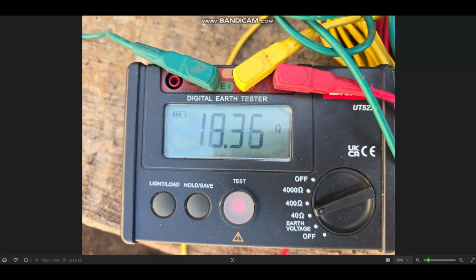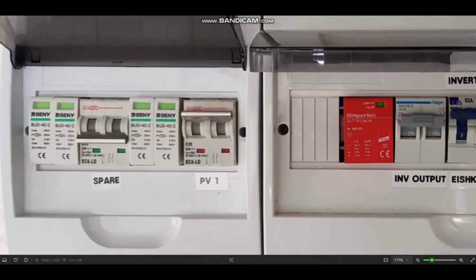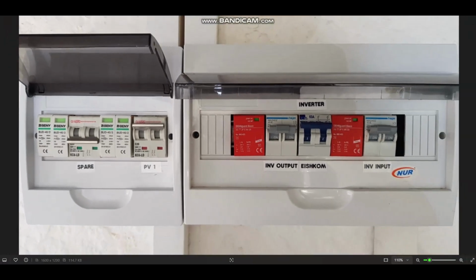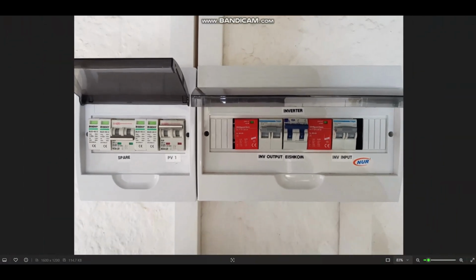What the earthing system is then linked to is a DC sub-DB, another distribution board. Here we can see, and again, you will need more surge arresters in the event that that voltage is exceeding what it should be. So at this point, I think it's important to mention the fact that what we've done here with the safety and surge protection system is to put high quality airbags, electronic stability program, ABS braking, your airbags, your crumple zones, your rebar zones, things like that. But it doesn't necessarily guarantee that when something horribly goes wrong, that everybody survives. This is the bare minimum.